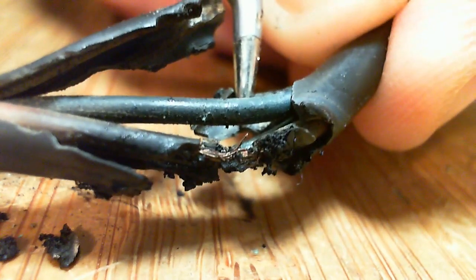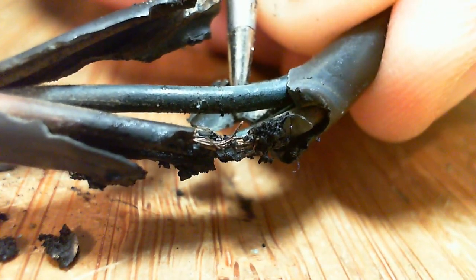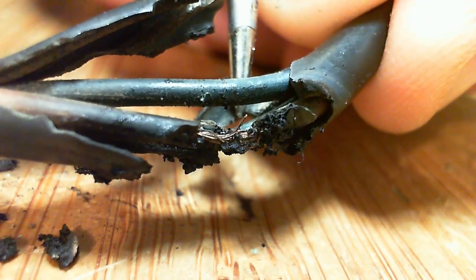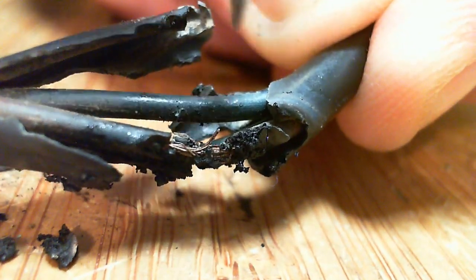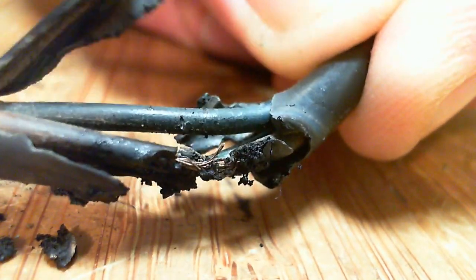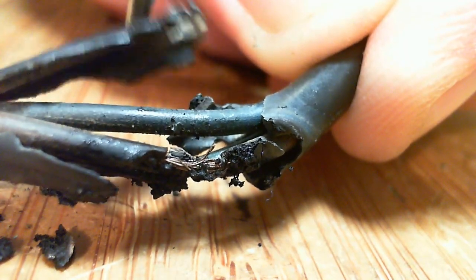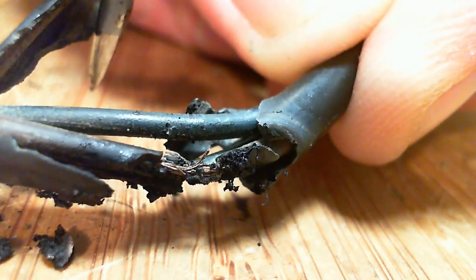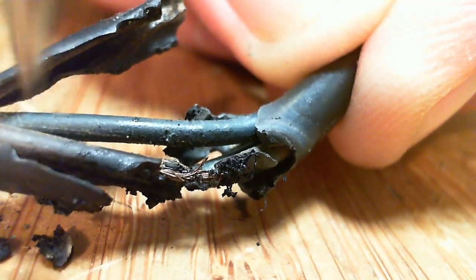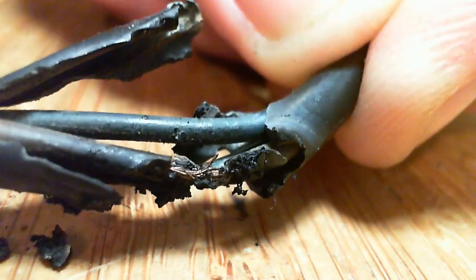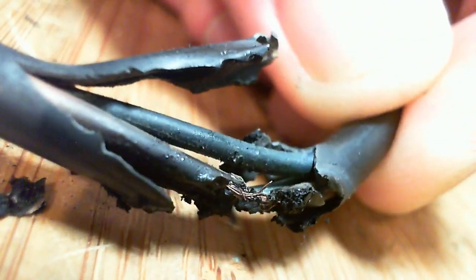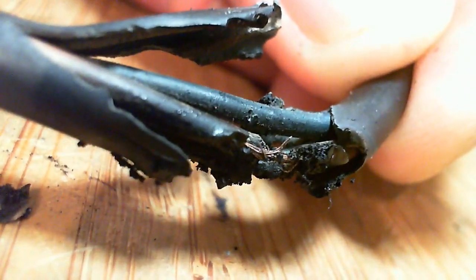This is a case of only a few strands carrying power and the wire getting hot, but not hot enough to damage the other wire, but hot enough to ruin the plastic cover, which is probably a different kind of plastic on the cover. We've got to open up this other wire. So what I'm going to do here is cut this right through here.